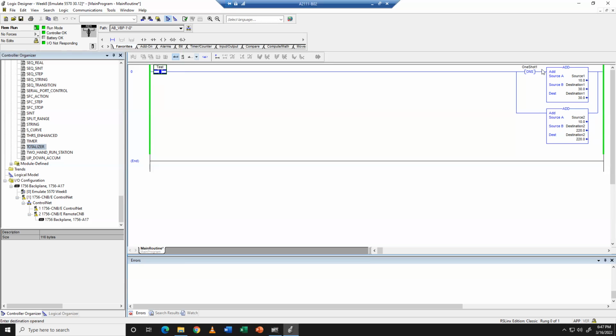Sometimes you need to make sure that something only happens once, because even though something may be on for a very short period of time, that is 22 cycles. So in the amount of time that this one only did one, this one calculated 22 tips. This is an example of when I have used one shots for this type of pulse flow meter calculation.